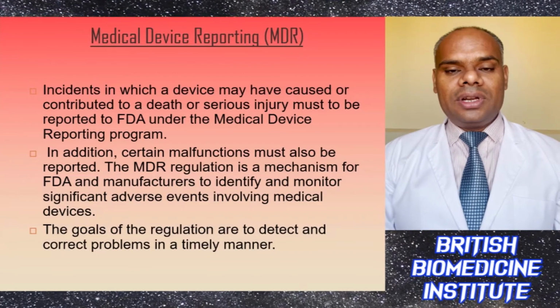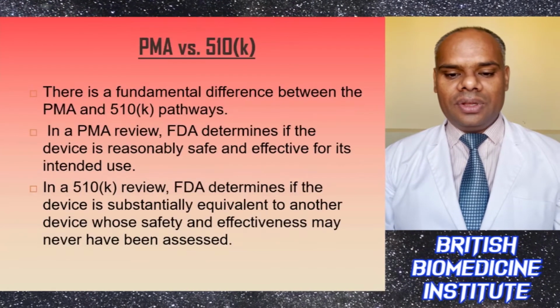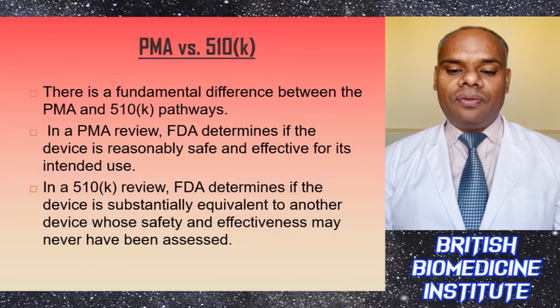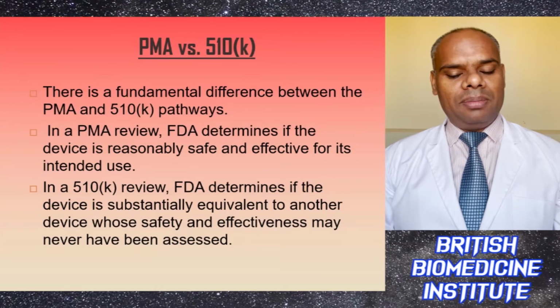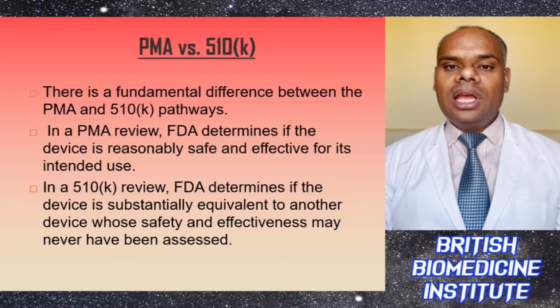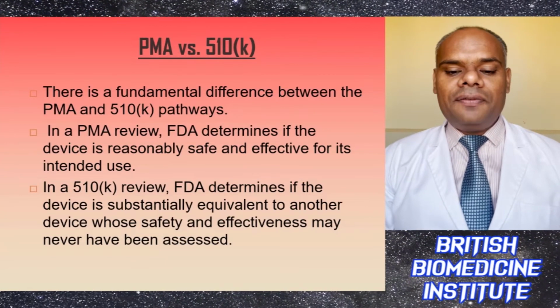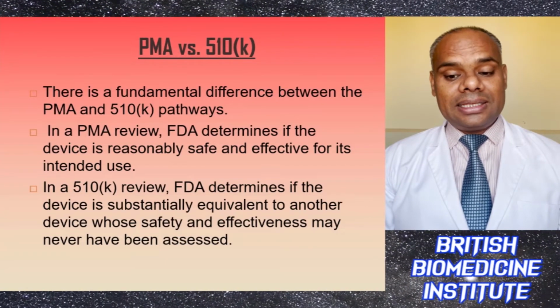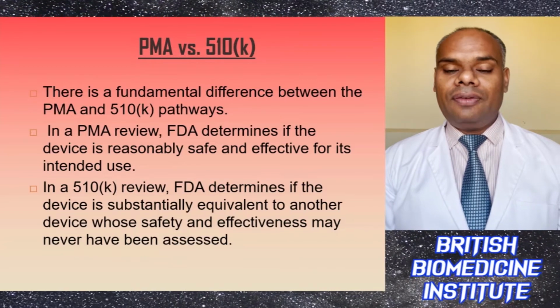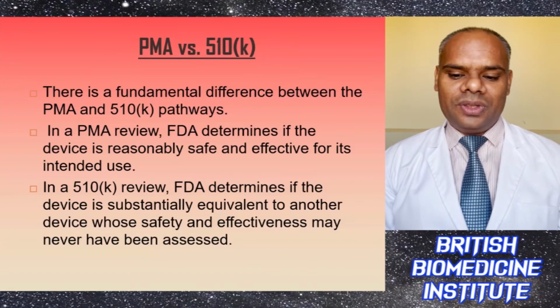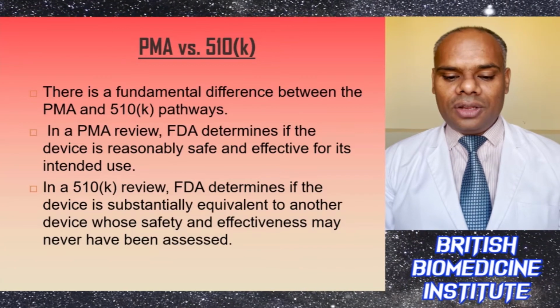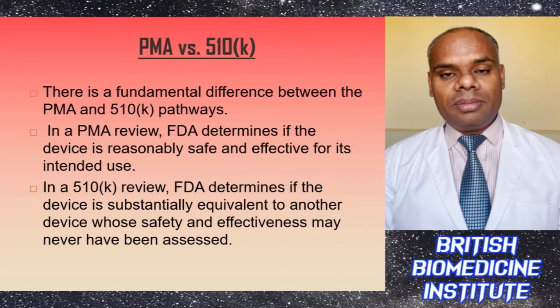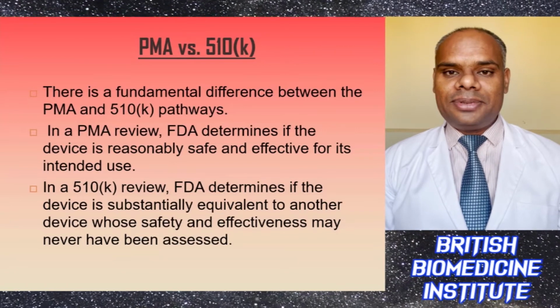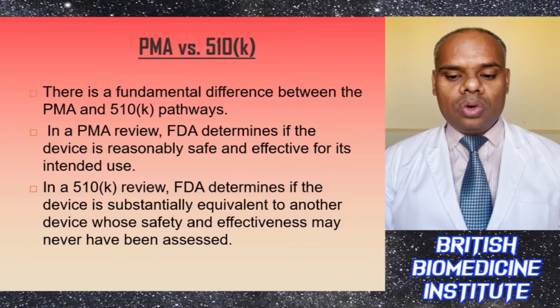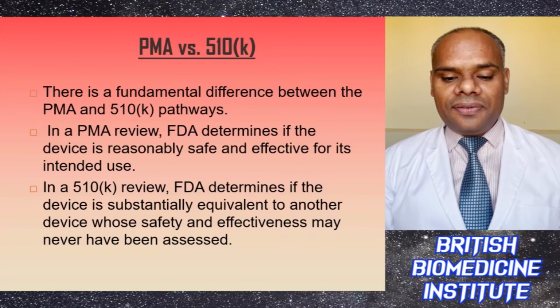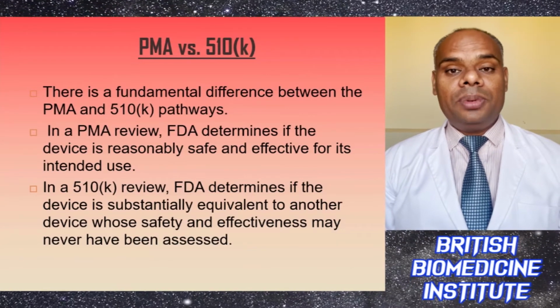So, PMA versus 510K application. Basically there is a functional difference between the PMA and 510K pathways. In PMA review, the FDA determines if the device is reasonably safe and effective for its intended use, and under 510K review, the FDA determines if the device is substantially equivalent to another device whose safety and effectiveness may never have been assessed.